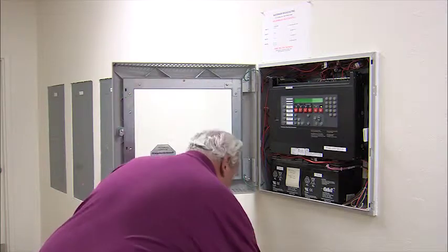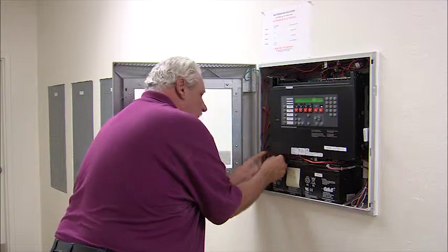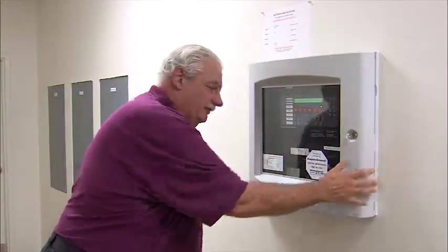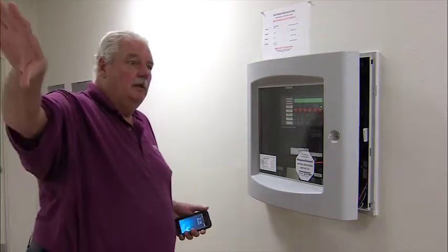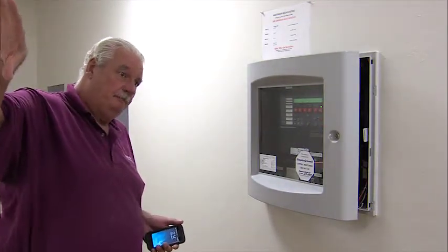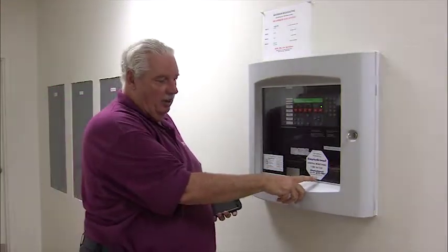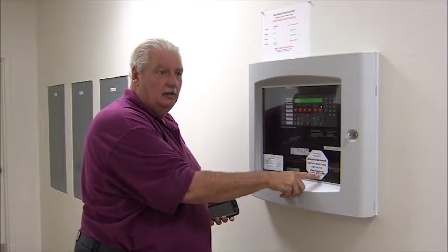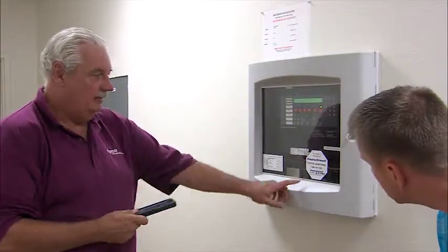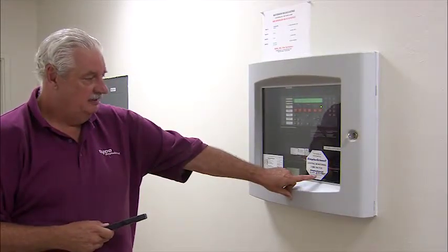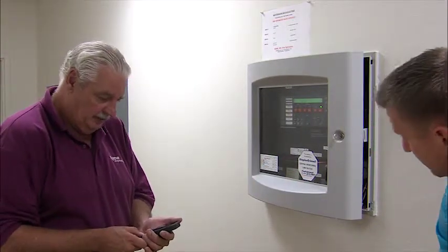See if I can do one here. For example, first thing I want to do is call the central station and put on a test. Anytime you have anybody in a building working on the system, either the sprinkler system, the chemical panel for the equipment rooms, you want to have them call this number and give them this account number. Let them know they're going to be working on the system, they want to put it on test. Okay? And there is a number on each of these. This number is on each panel.